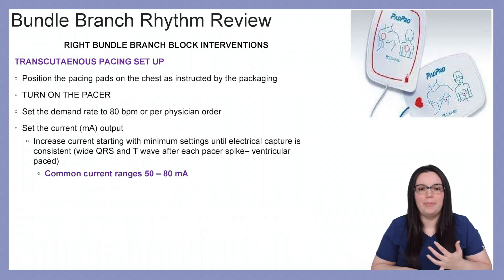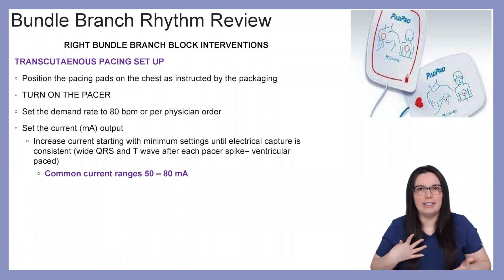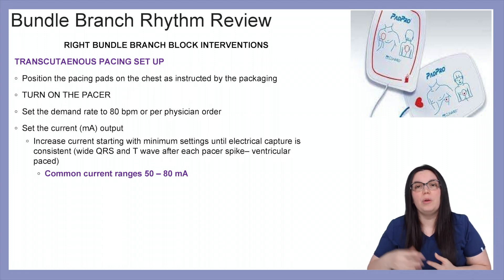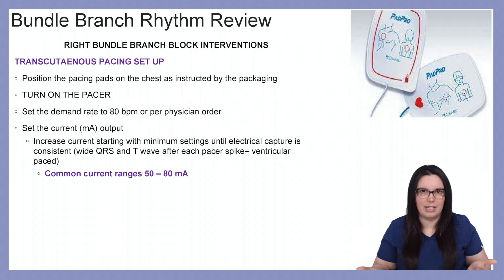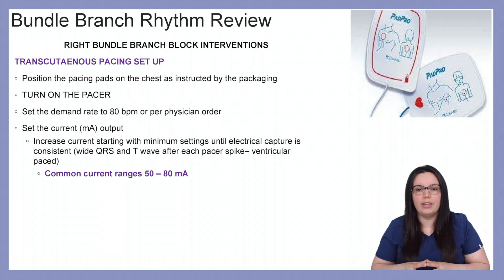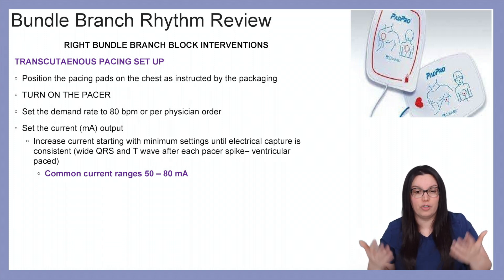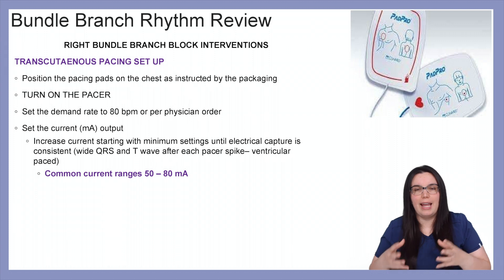So how do we set up transcutaneous pacing? We position the pacing pads on the patient as instructed by the packaging — normally one pad goes over the right anterior chest wall and the left pad goes on the left mid-axillary line next to the heart. Turn on the pacer first, then set the demand rate to 80 beats per minute or whatever the physician orders. Set the current mA output by starting at the minimum and increasing until electrical capture is consistent, shown by a wide QRS and a T wave after each pacer spike. Common current range is between 50 to 80 mAs.